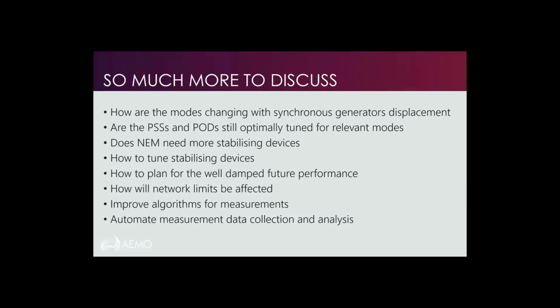They may. If grid forming is controlling voltage more than power to synchronize better to the network frequency and voltage, and grid forming leaves electrical power to oscillate a bit more, like with non-grid forming inverters, it could happen. But I'm really guessing here, it's just my intuition. I'm not 100%. I don't think anyone is 100% at the moment with grid-forming inverters.